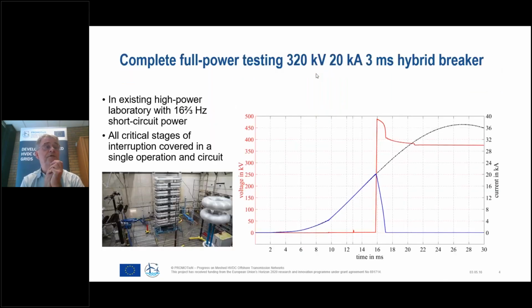This picture shows the proof of the pudding I was talking about. The key point in testing opportunities is that we were able to design test circuits in an existing high power AC lab, meaning no major costs had to be made erecting a specialized DC lab for doing DC tests. The trick is we run our generators at a low frequency, 16 and two-thirds Hertz, which means we can create a pseudo DC environment. With that, we are able to replicate all the critical stages of current interruption.